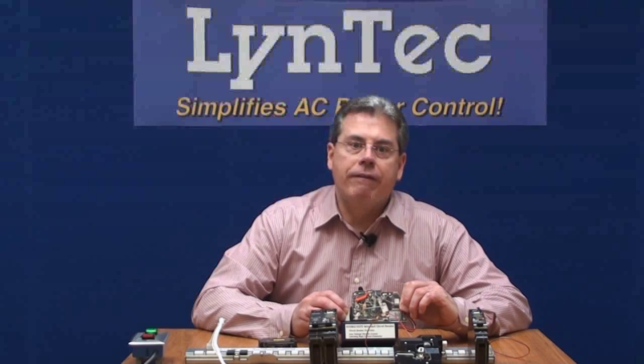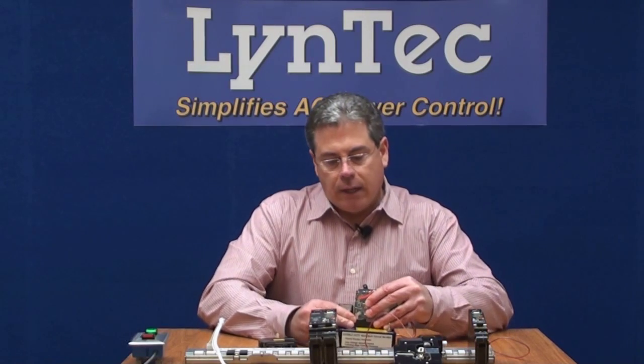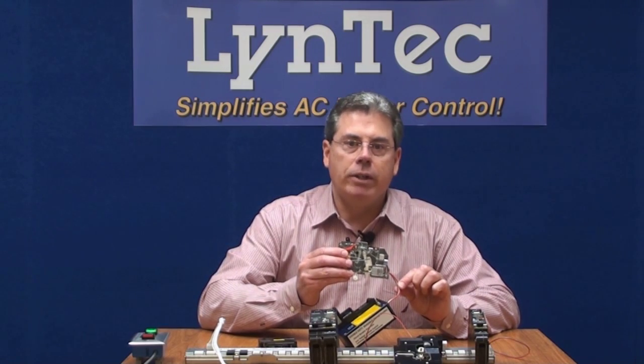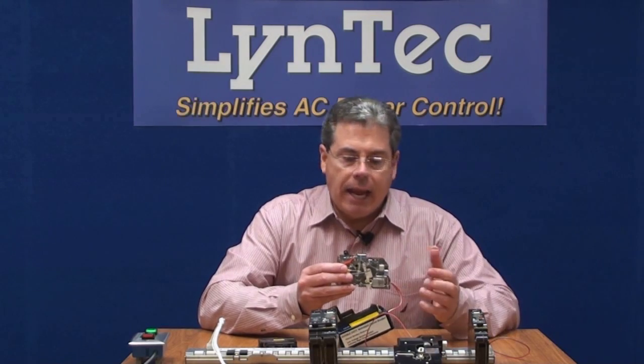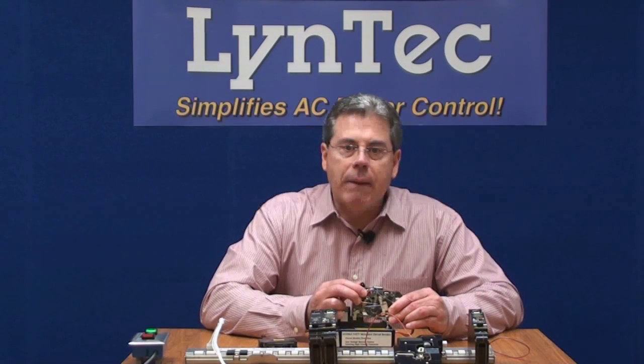The QO compatible motorized breaker fits into any standard Square D load center or panel board, so these are retrofittable if there's an existing QO compatible panel on the wall. You wire the breaker the same as any standard circuit breaker — the hots, neutrals, and grounds wire just like every circuit breaker out there. All you have to do is connect the end of a sixty-inch low-voltage control wire pigtail to the LynTec electronics in a sidecar, and that's all you need. The driver board that LynTec makes and puts into the sidecar does the rest for you.